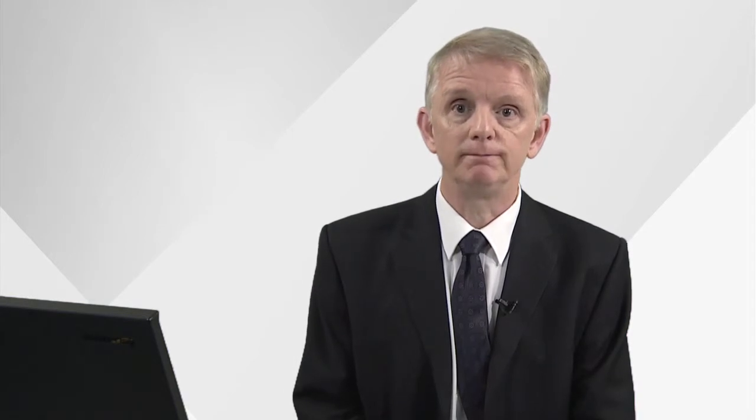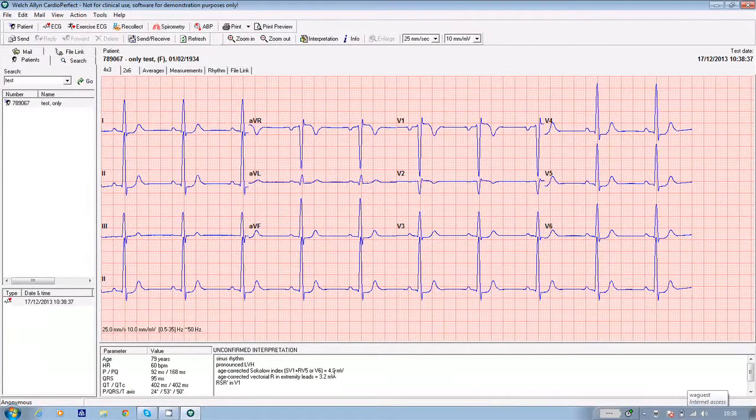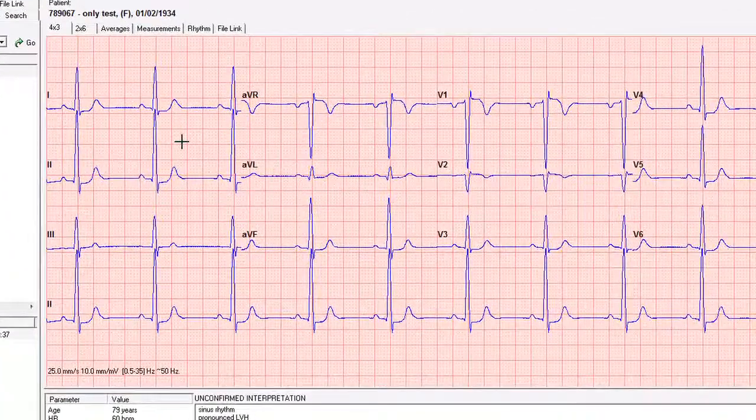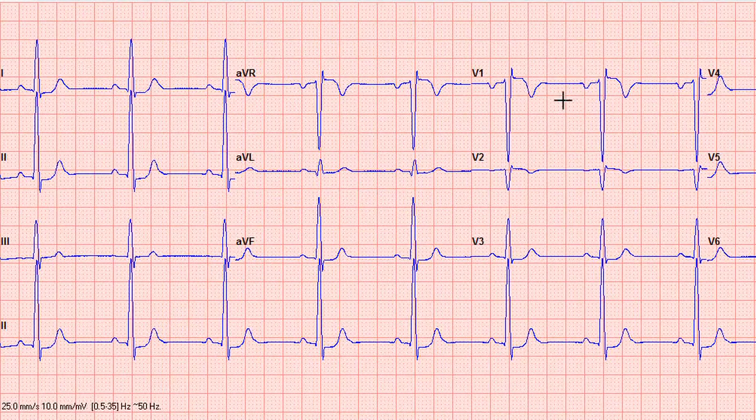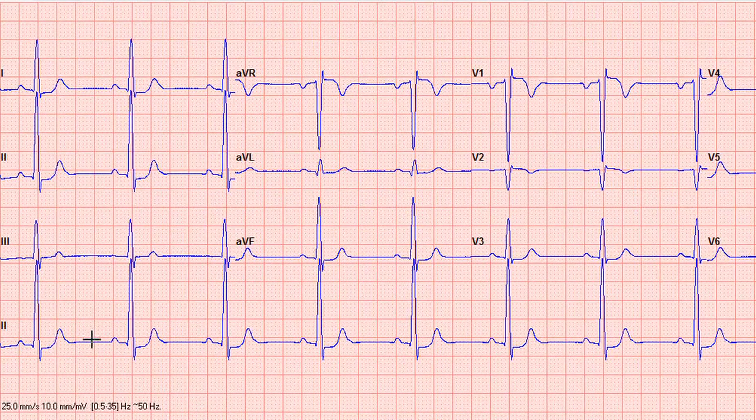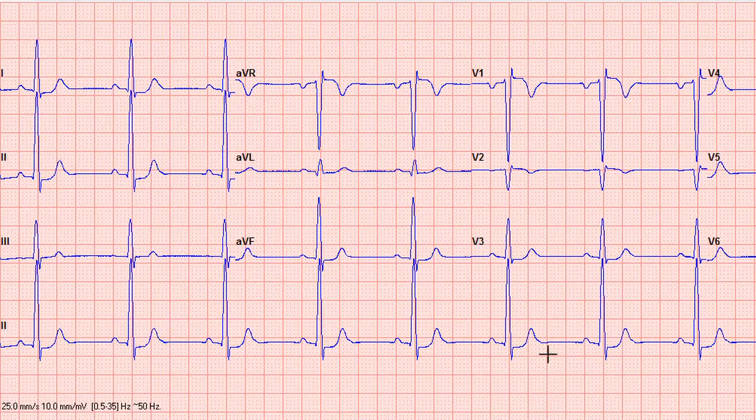After recording the ECG, the test is automatically saved to our software and a PDF copy of the test can be sent to your file output directory and from there it can be attached to the individual's patient record. The standard format of the ECG will be three lines with four leads on each and at the bottom a lead two rhythm strip.